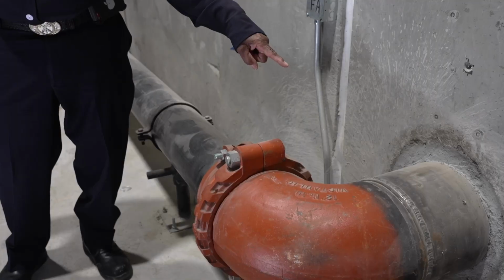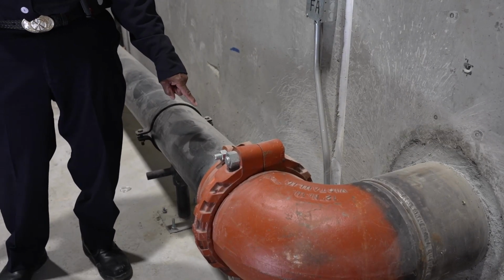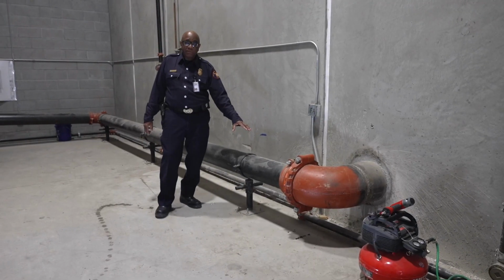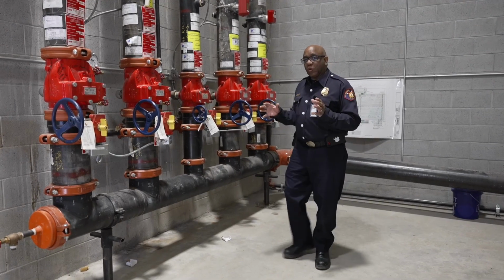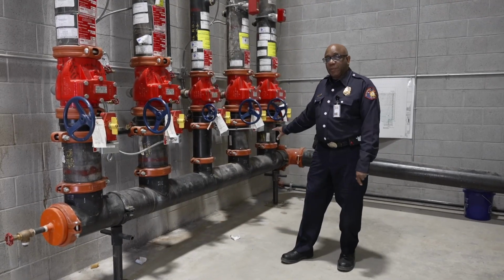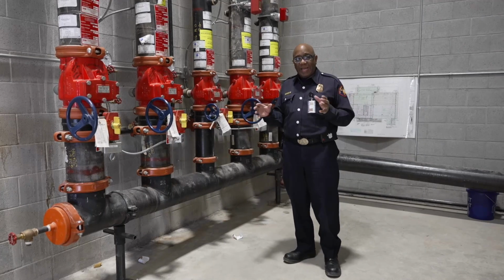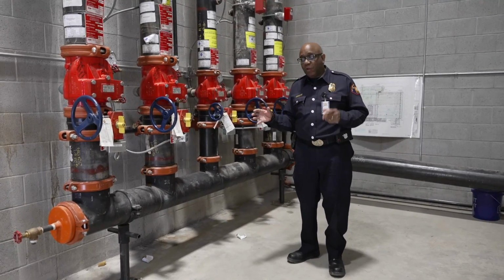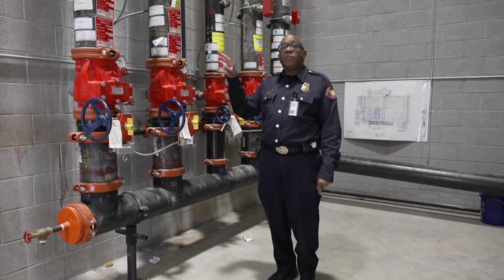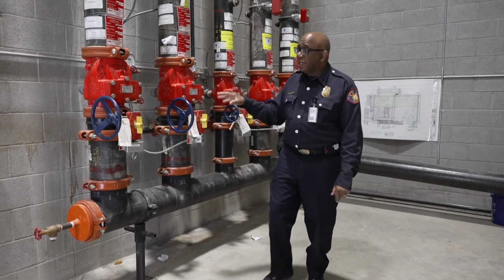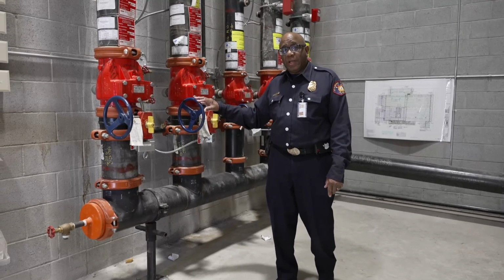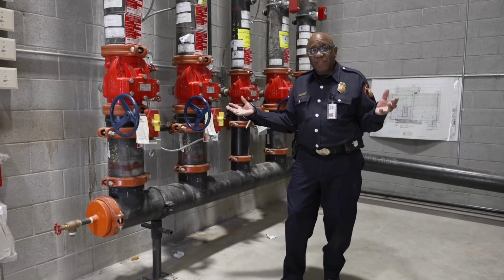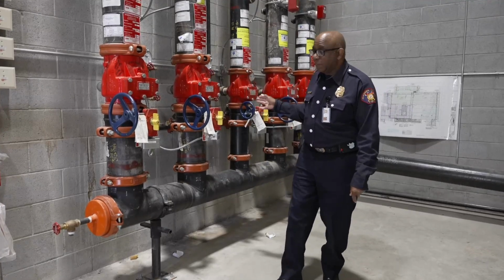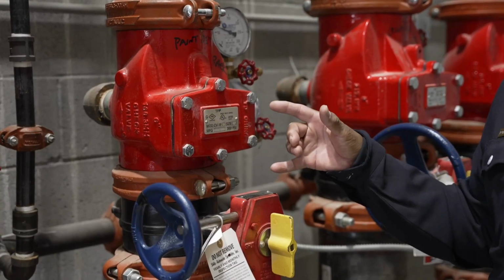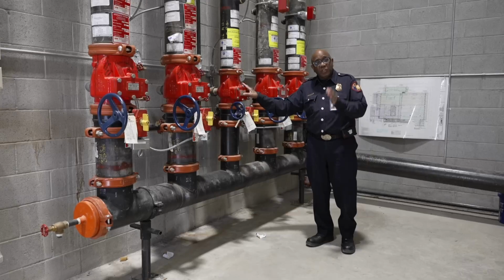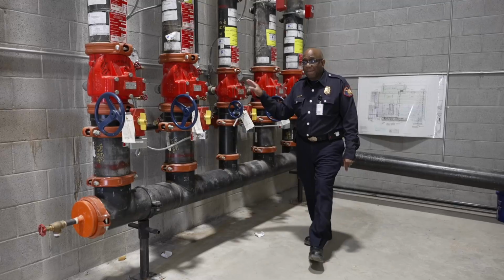Here we have a 10-inch water supply, fire water supply, necking down to an 8-inch. Many of the big box stores are in a manifold style system. The reason for that, you have a maximum capacity of somewhere between 25,000 and 40,000 per system. In the case of a big box store, mercantile like this, the maximum will be a 25,000 area. This store is well over 25,000, so they have 4 separate zones. They also have, for the in-rack, a separate zone for that. We'll see the in-rack in a little while, in-rack sprinklers.